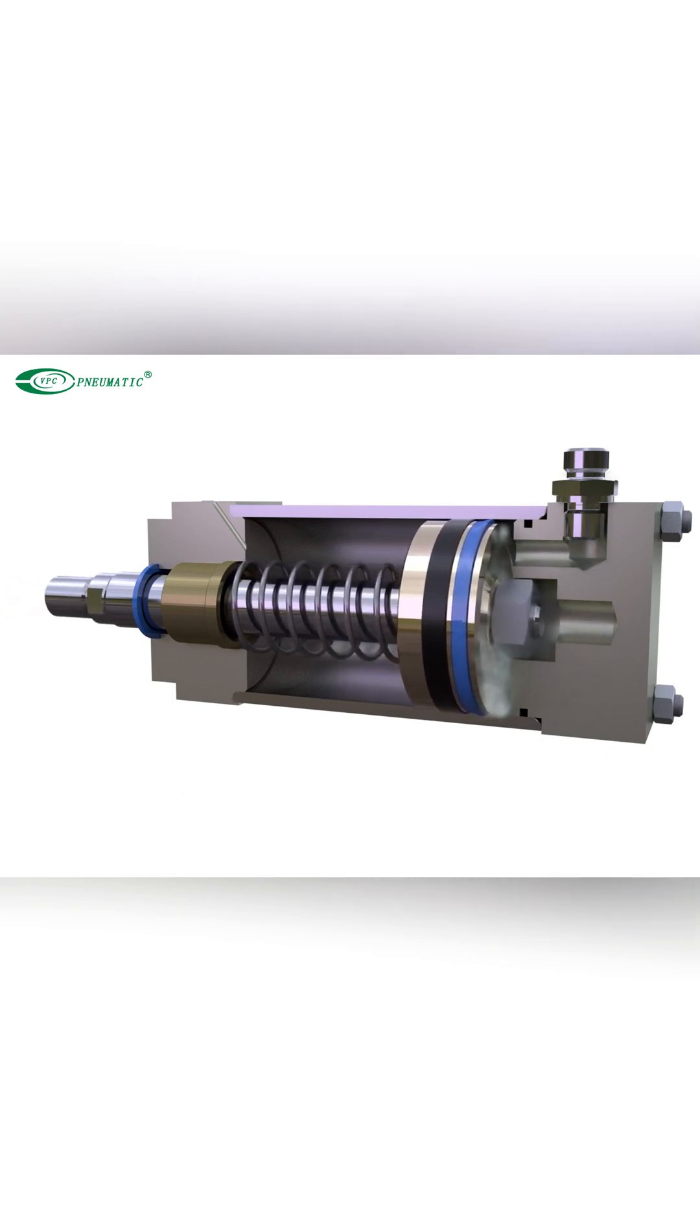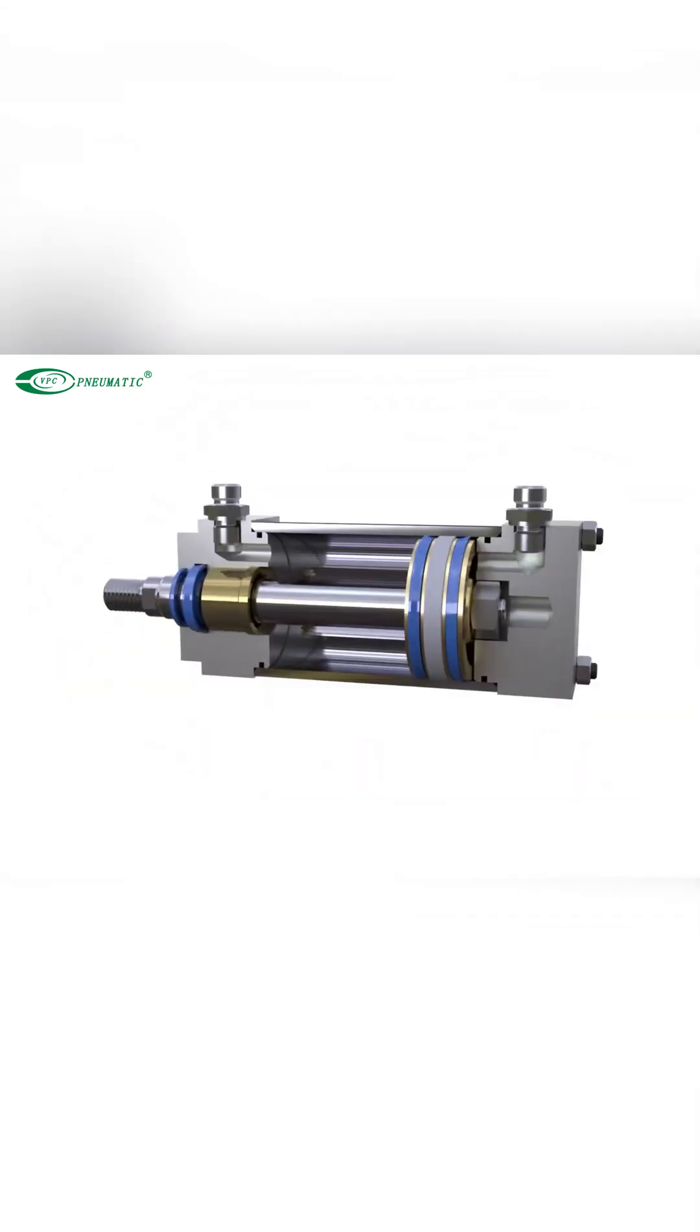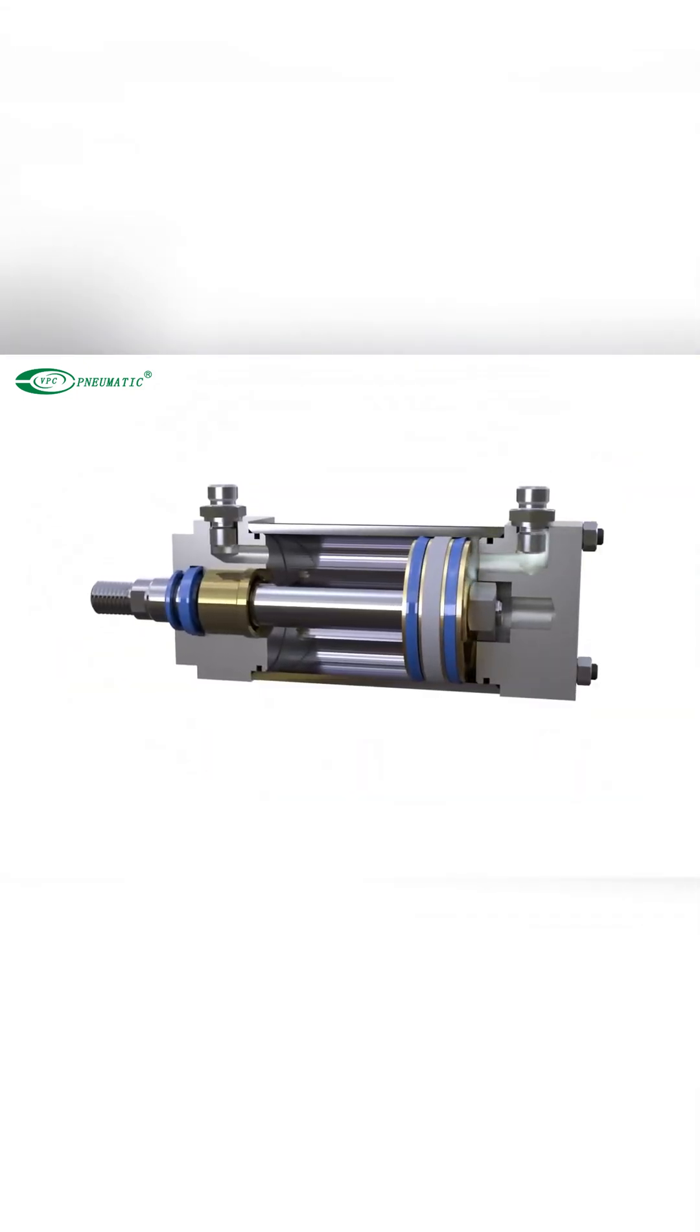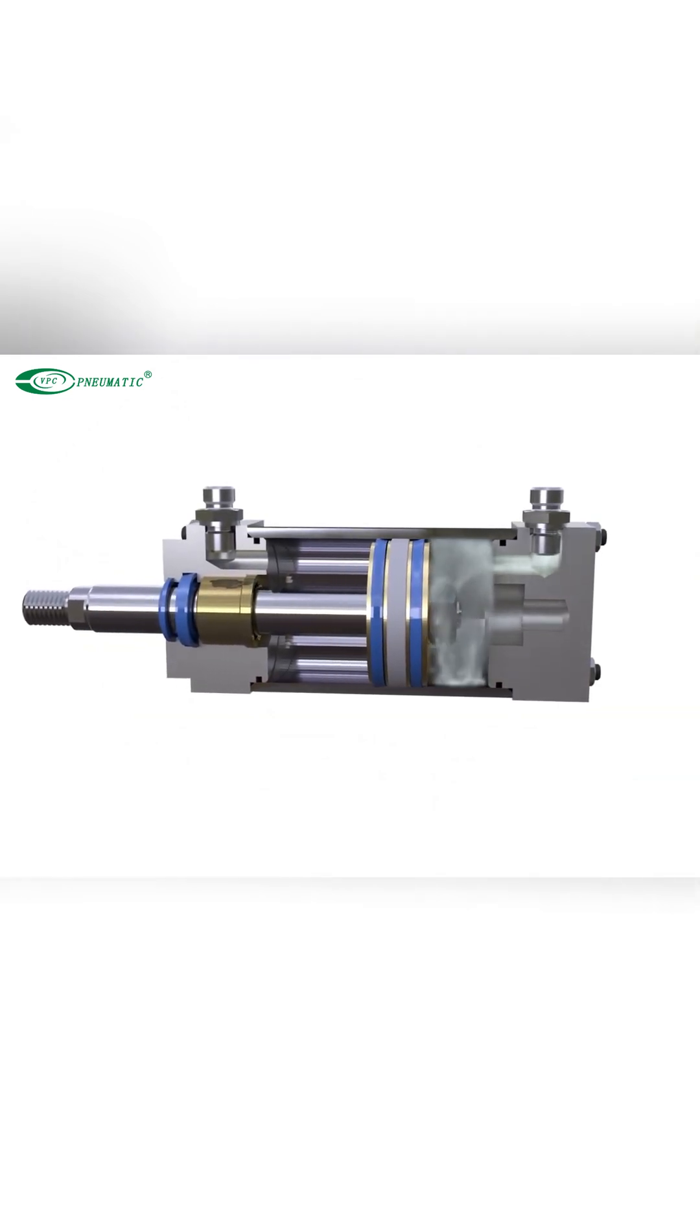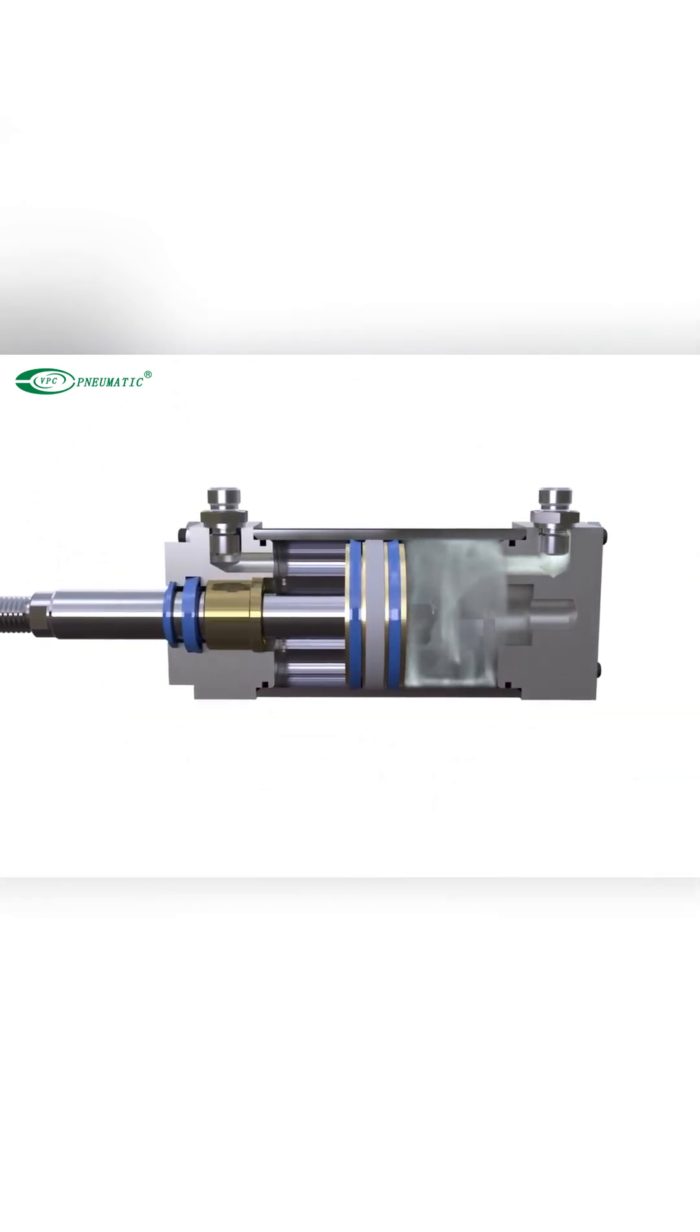Use clean and dry compressed air as working medium in accordance with the corresponding working air pressure. The piping should be fully blown clean to prevent impurities from entering the system, which can cause the cylinder or solenoid valve to malfunction.